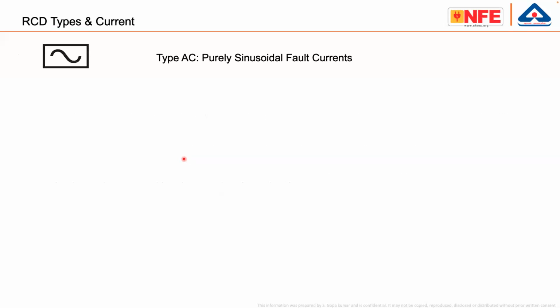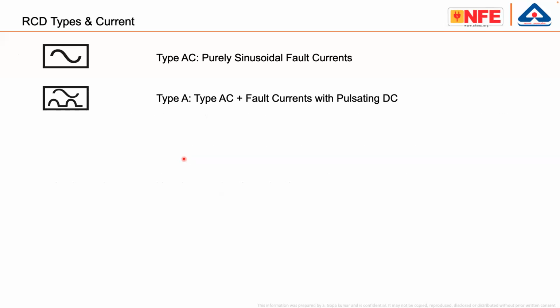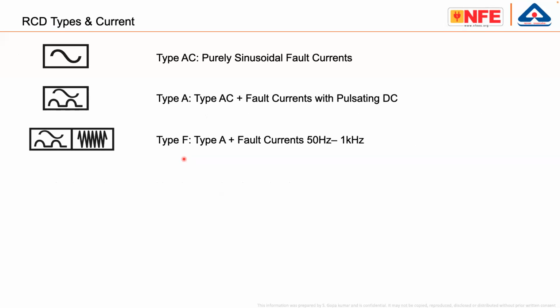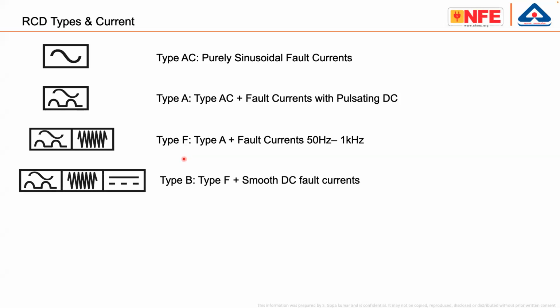Now let us look at different types of RCDs. RCDs are of four categories. The first one is type AC RCD, which is for purely sinusoidal fault current. Type A is for the sinusoidal current plus, that means type AC plus, additionally it gives protection against fault current from pulsating DC. We have type F, which has the characteristics of type A plus fault current up to 1 kilohertz frequency. Also, we have type B RCD, which has the characteristics up to type F and additionally smooth DC currents.